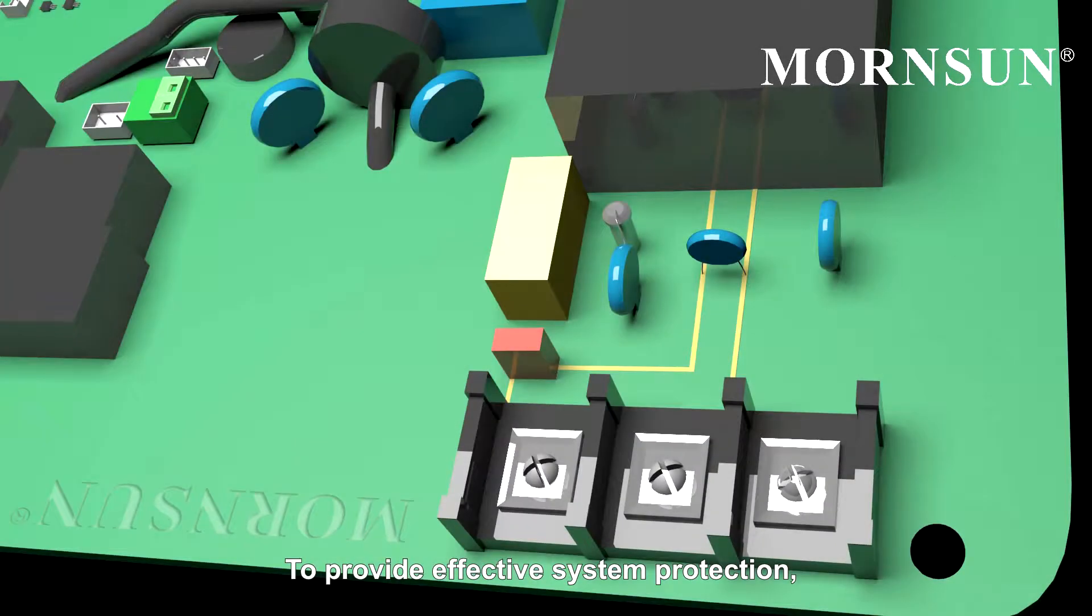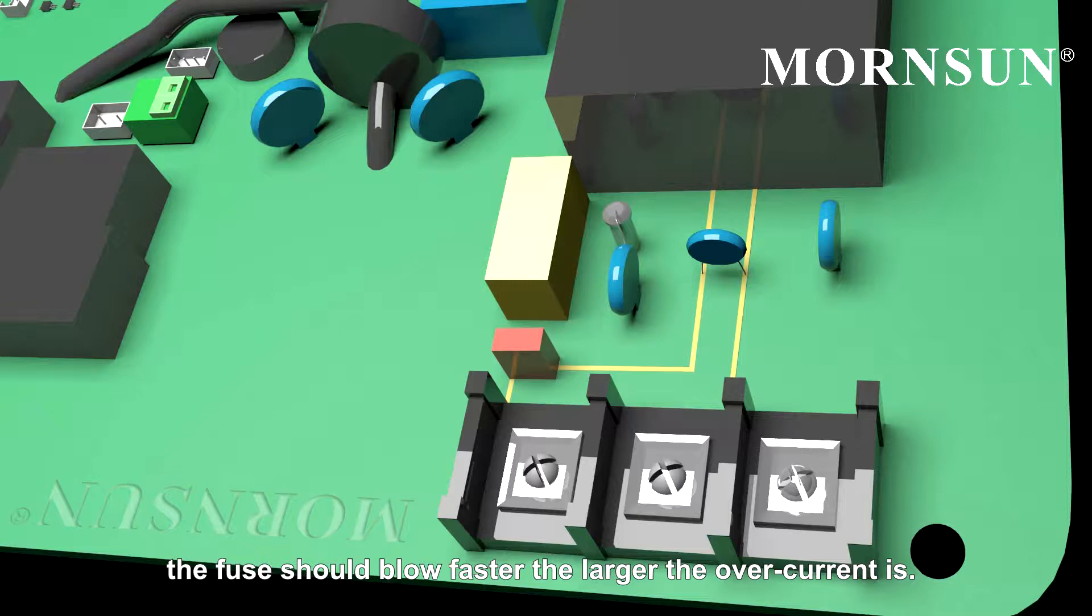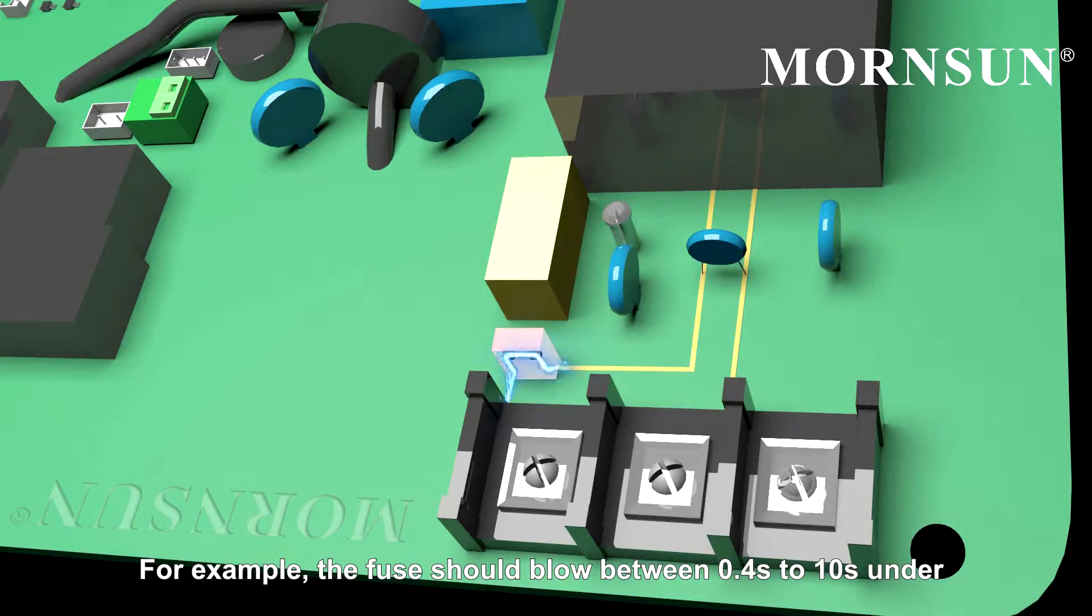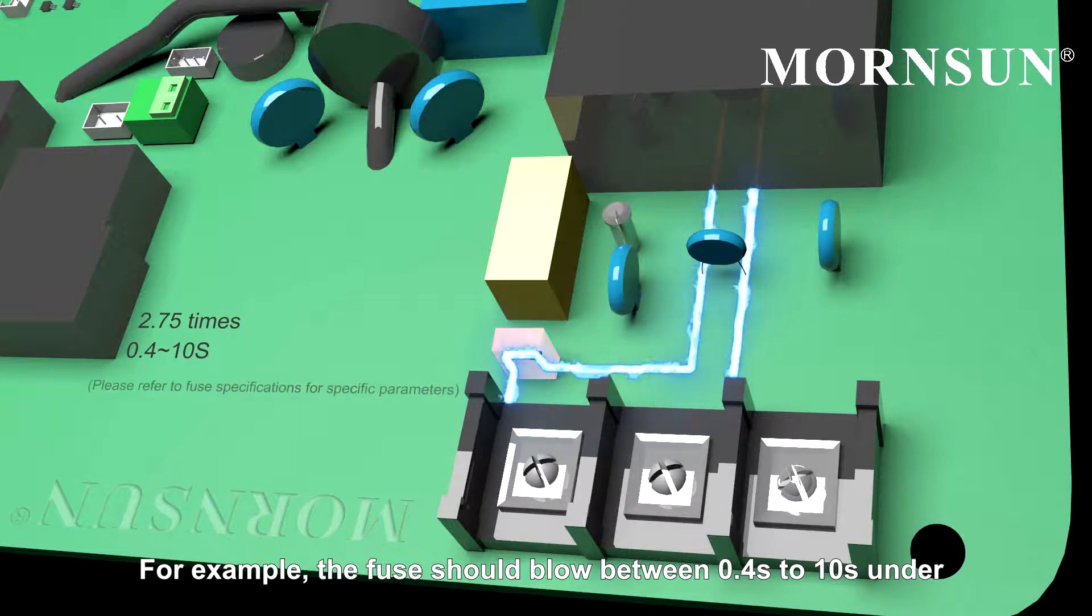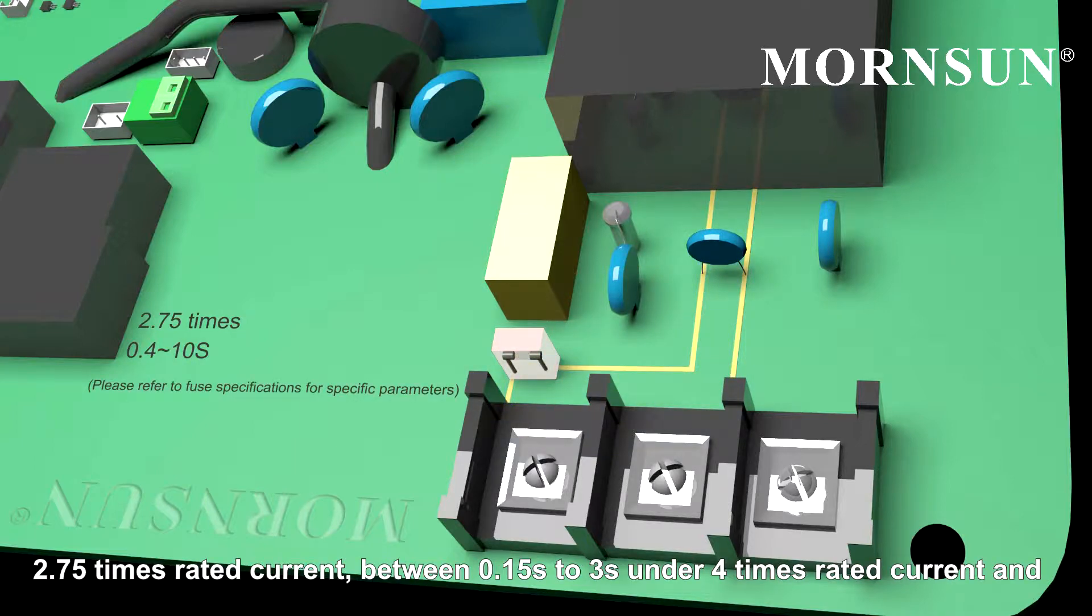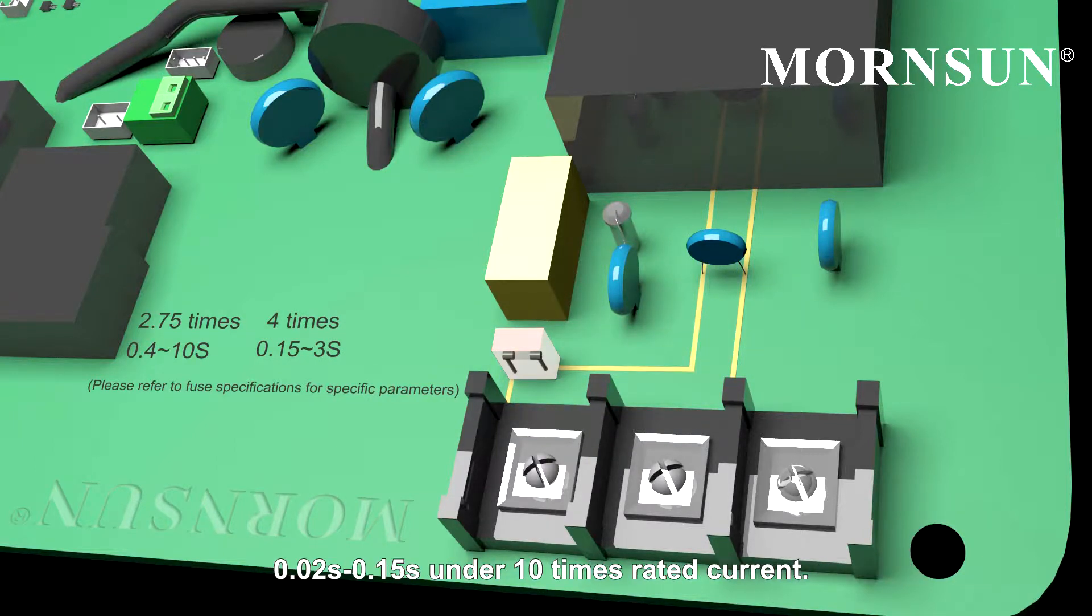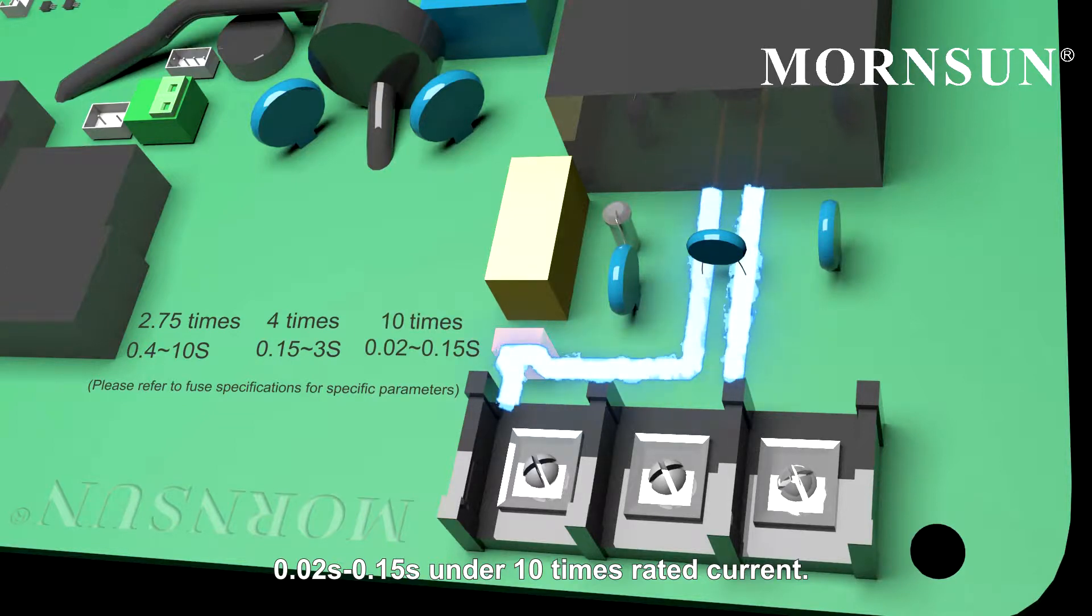To provide effective system protection, the fuse should blow faster the larger the overcurrent is. For example, the fuse should blow between 0.4 seconds to 10 seconds under 2.75 times rated current, between 0.15 seconds to 3 seconds under 4 times rated current, and 0.02 seconds to 0.15 seconds under 10 times rated current.